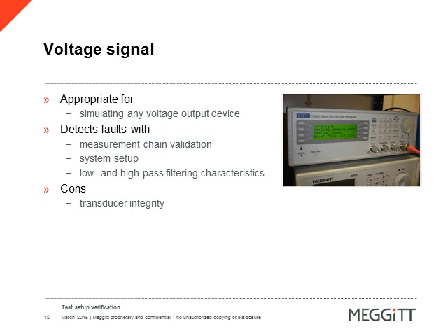A function generator or handheld signal source allows the use of a calibrated signal that varies both in amplitude and frequency. This is a more thorough method that can be used to verify gain, scaling settings, and even the filter roll-off values for each channel. This is a very good system verification test method for a voltage output transducer. But remember, with other test methods, the transducer itself can be verified as well. Other simulation methods can be done for IEPE devices.